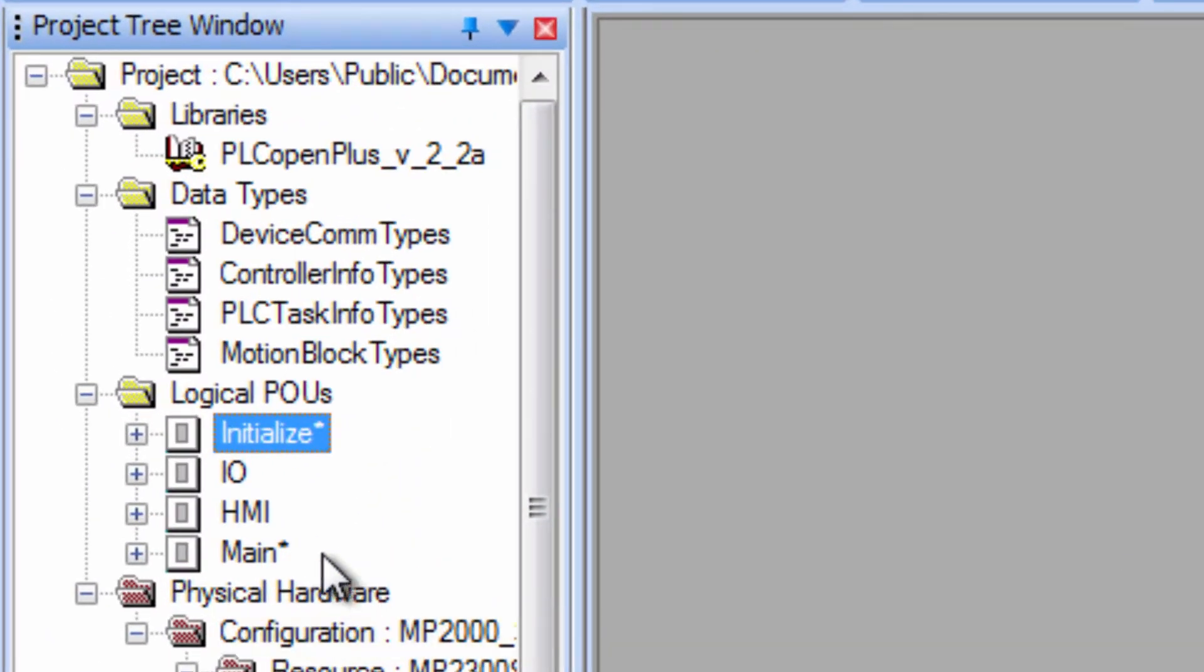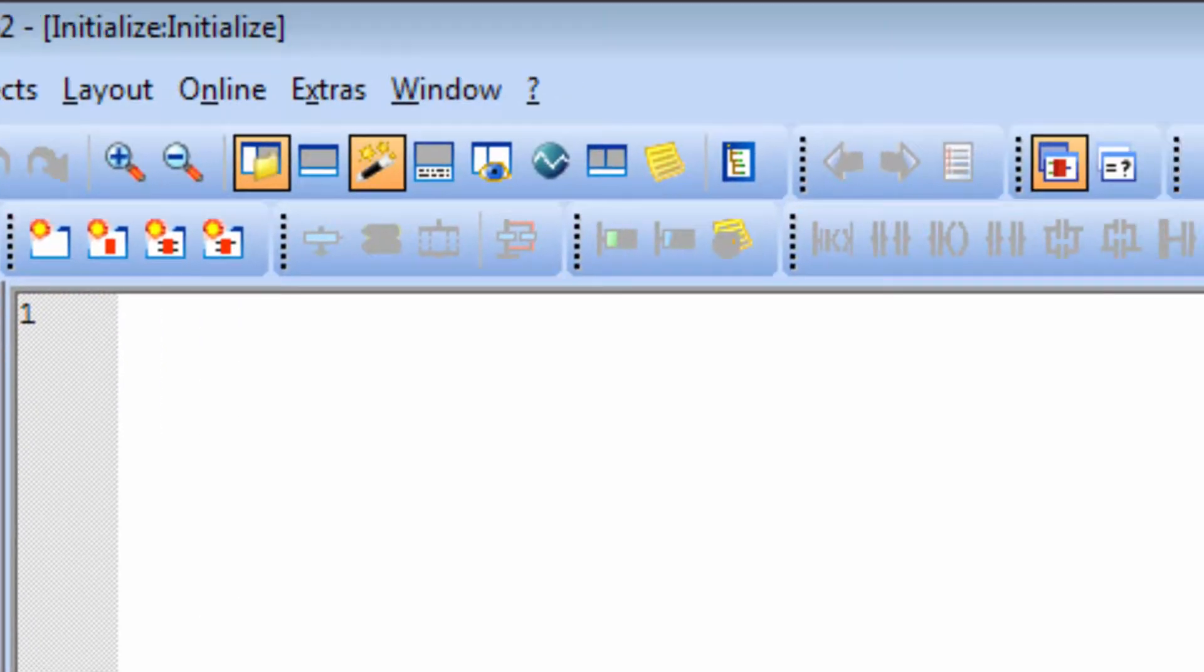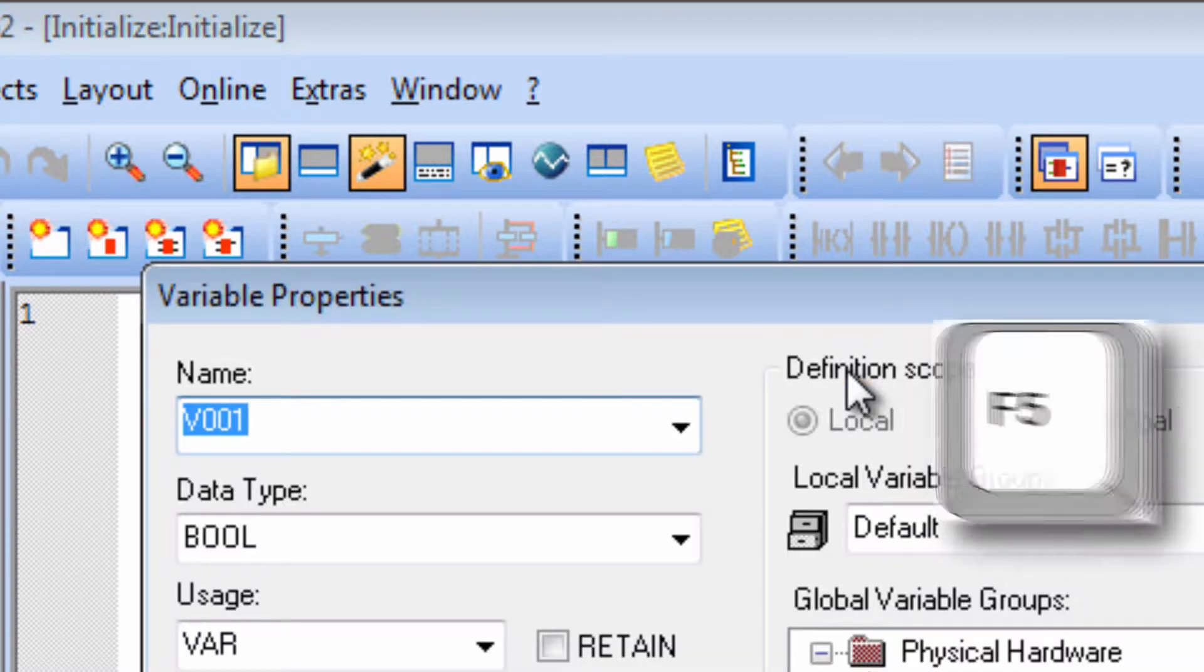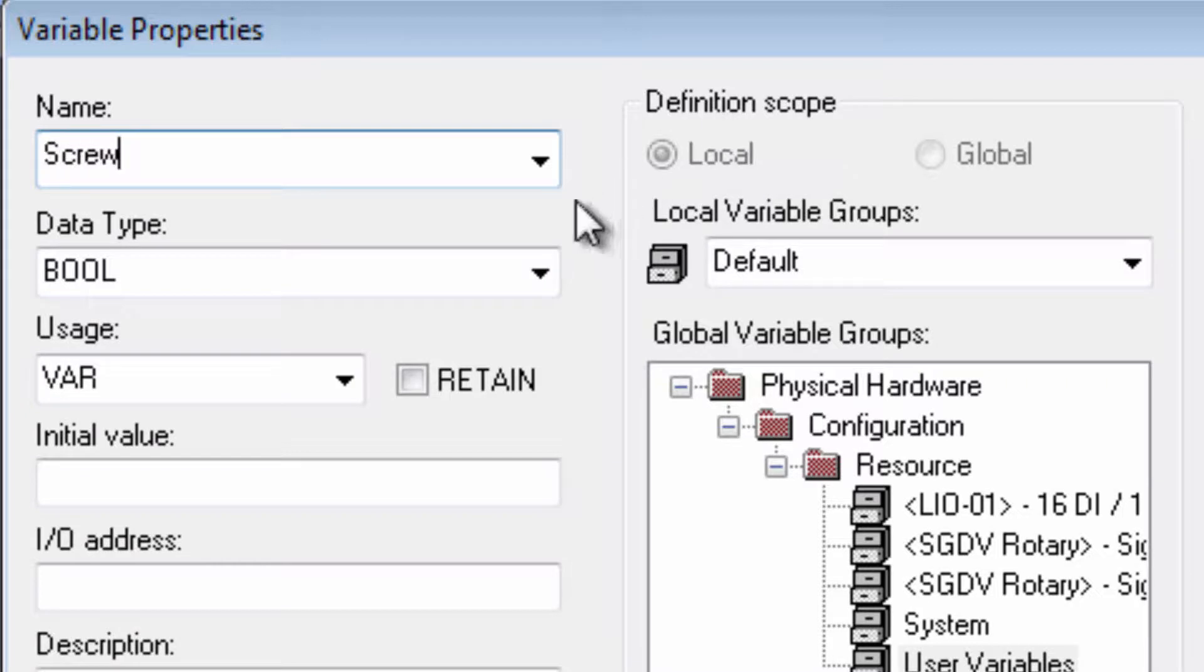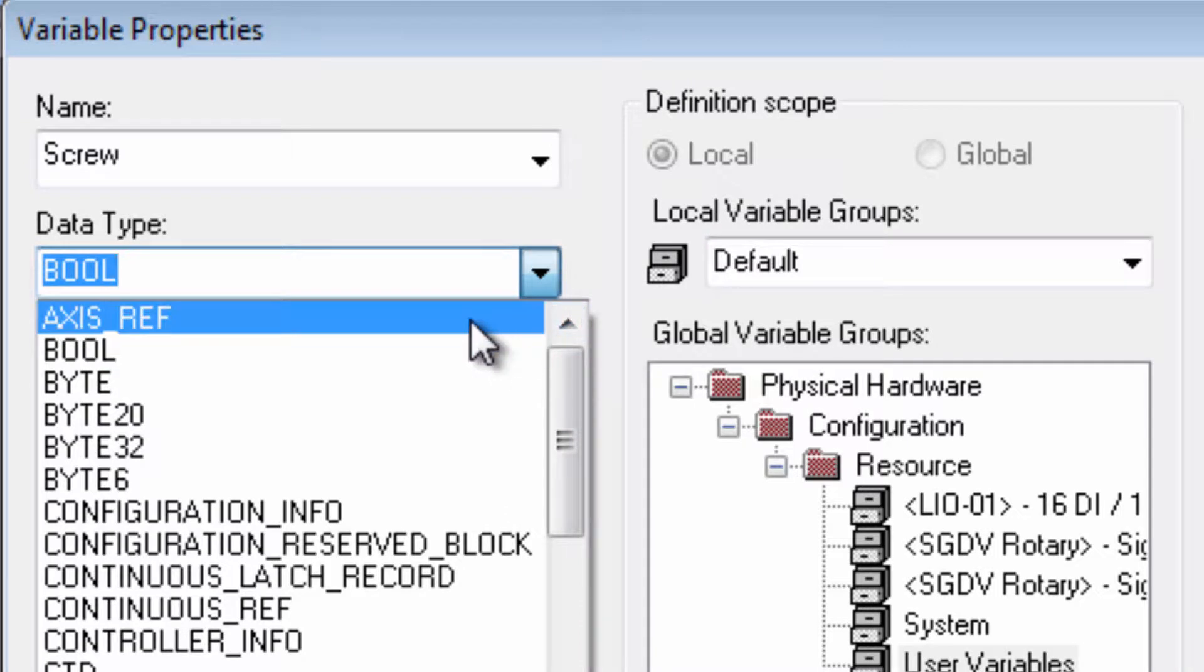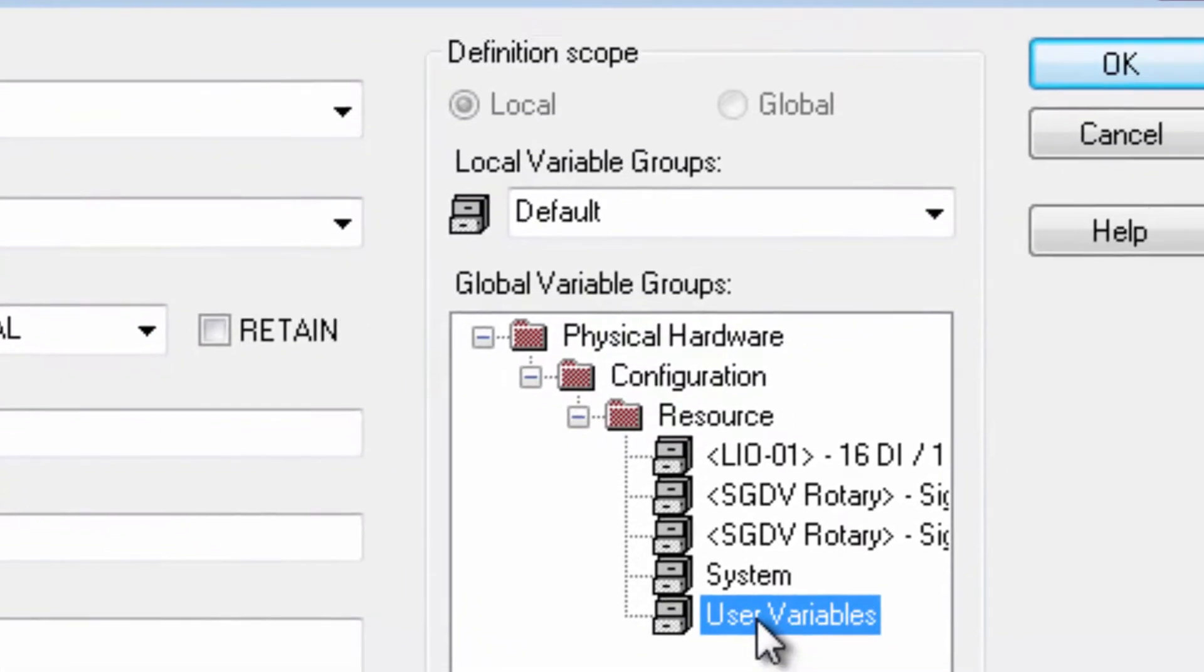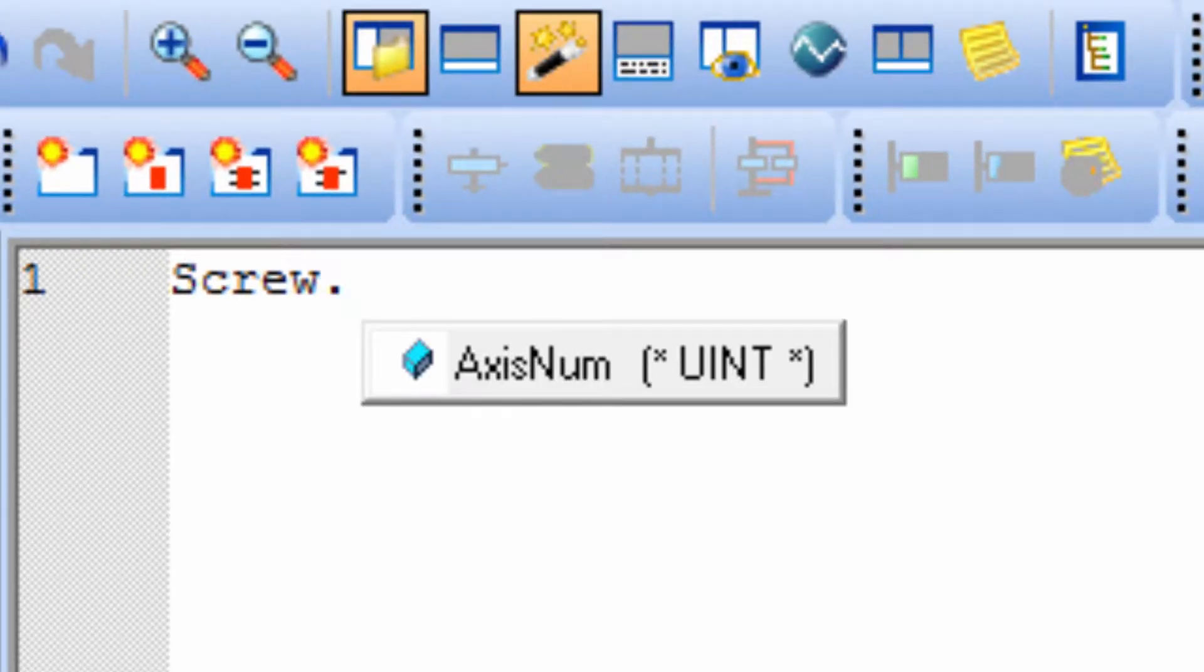We recommend defining the Axis variables inside the Initialize program POU. Initialize uses the Structured Text Language, so use the F5 key or right-click Insert Variable. I'll name the variable for this first axis as Screw. Under Data Type, choose AXIS_REF. Usage is VarGlobal so that this variable can be used anywhere in the project. I'll organize the variable under the User Variable group and click OK.